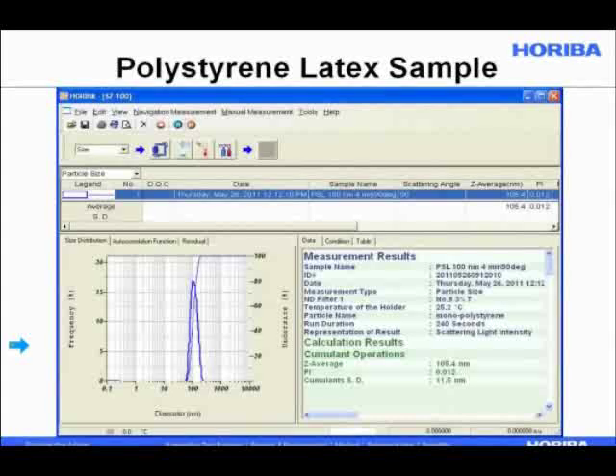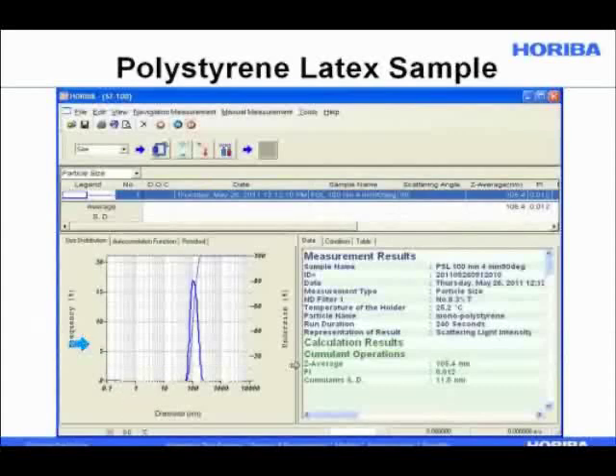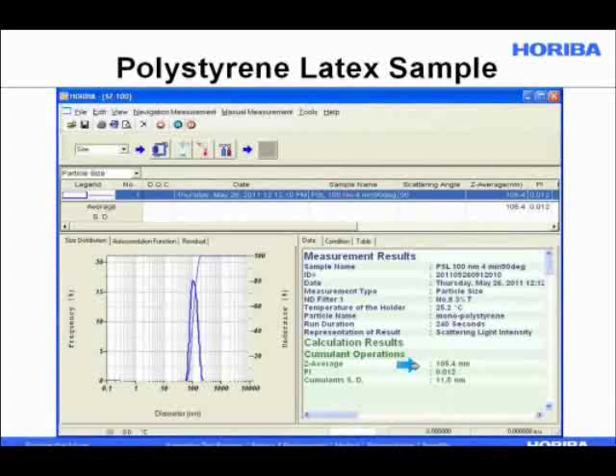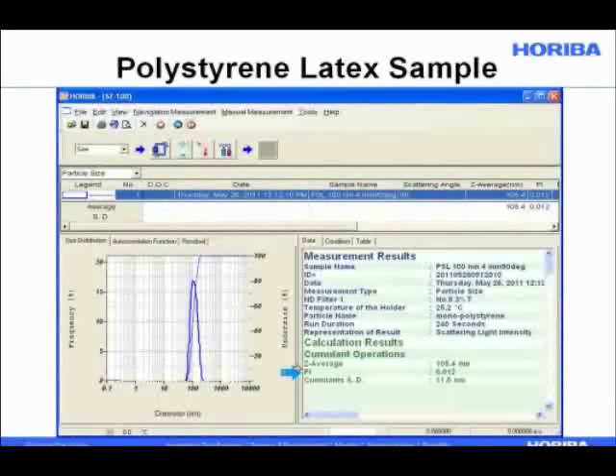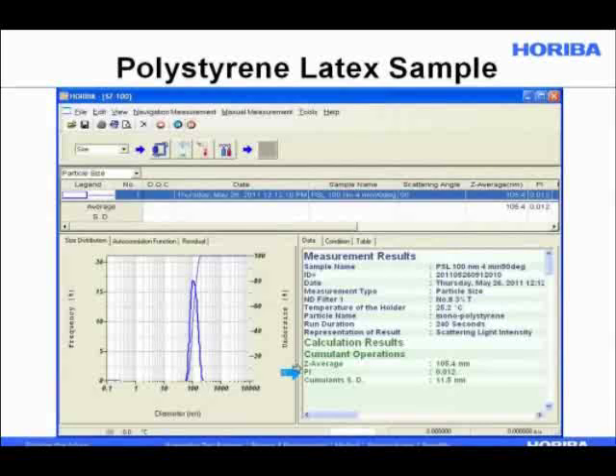Here is a measurement with the SZ100 on a polystyrene latex sample. The plot shows frequency as a function of diameter. The z-average size comes out at 105 nanometers, very close to the nominal 103 nanometers, with a quite low polydispersity index — as expected for a narrow polystyrene latex sample. Polystyrene latexes come up a lot in this field because they are fairly easy to obtain and handle, and because the latex industry has driven much of the development of particle sizing, particularly dynamic light scattering.